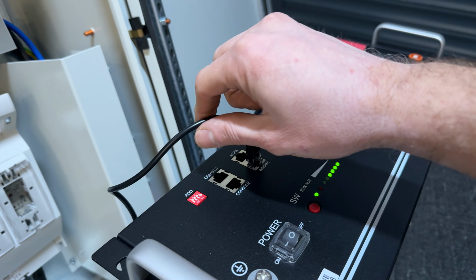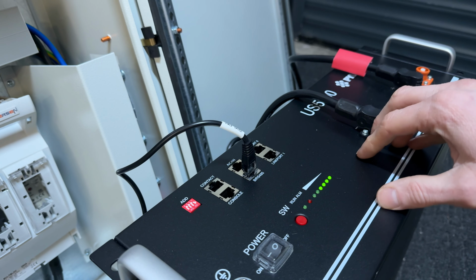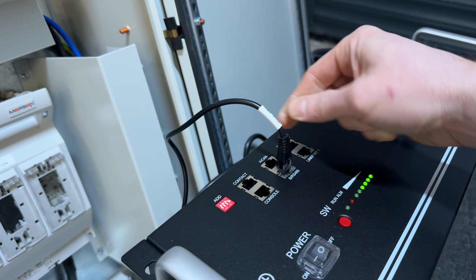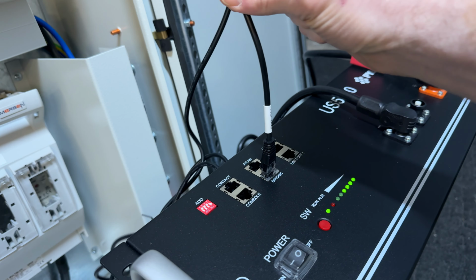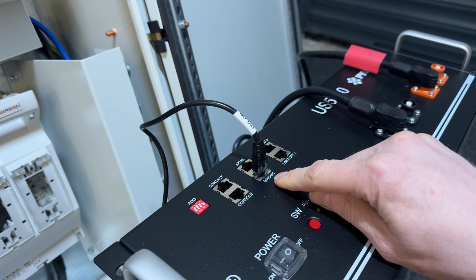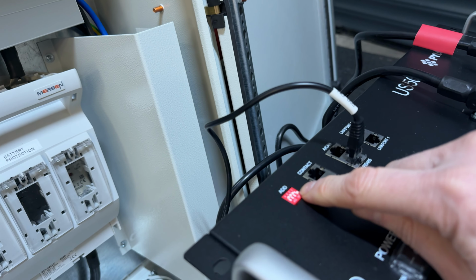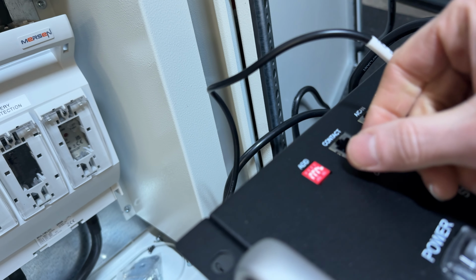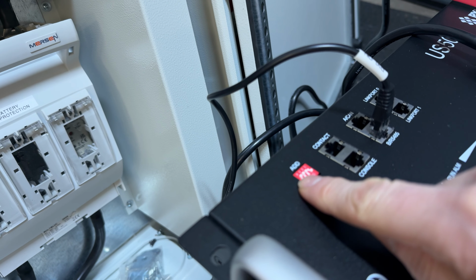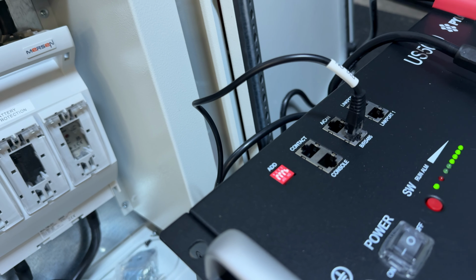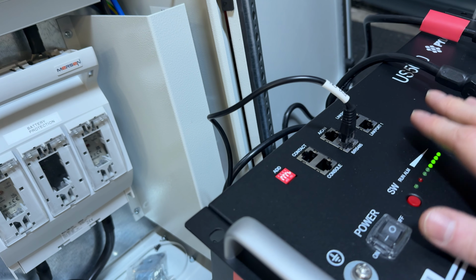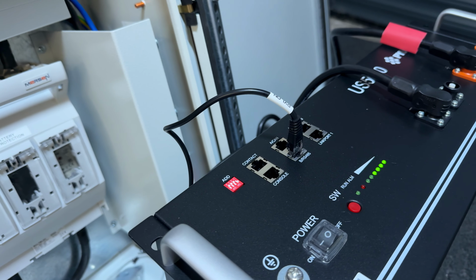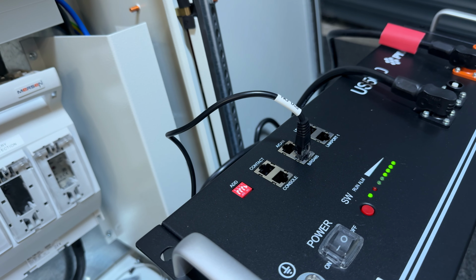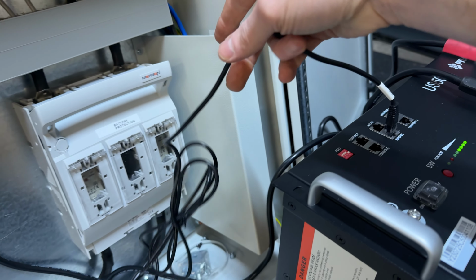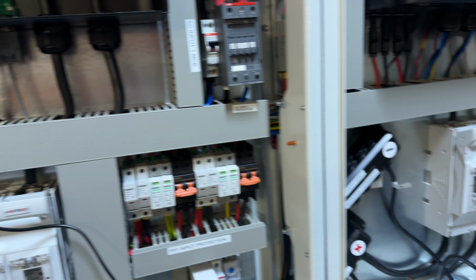If you decide to go with Pylontech, remember the first Pylontech battery is always the master battery. And we connect this cable, and no other cable, only this particular cable, to the RS485 port. And the dip switch 1 needs to be moved down. Switches 2, 3 and 4 remain at the default settings. That's only for the master battery. The second, third, fourth, etc., should remain unchanged. The other end of the BMS cable is connected to the battery port here.